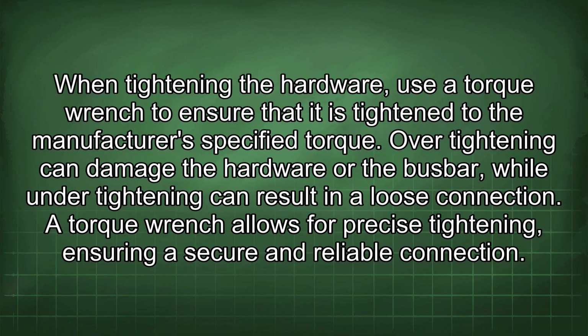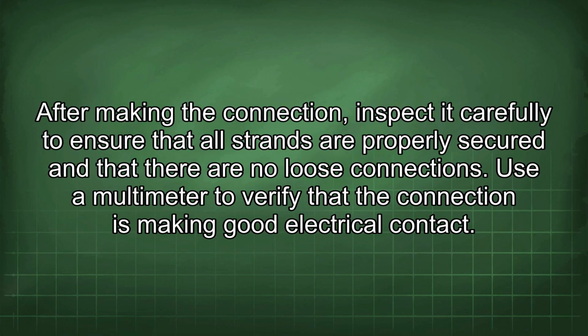When tightening the hardware, use a torque wrench to ensure that it is tightened to the manufacturer's specified torque. Over-tightening can damage the hardware or the busbar, while under-tightening can result in a loose connection. A torque wrench allows for precise tightening, ensuring a secure and reliable connection. After making the connection, inspect it carefully to ensure that all strands are properly secured and that there are no loose connections. Use a multimeter to verify that the connection is making good electrical contact.